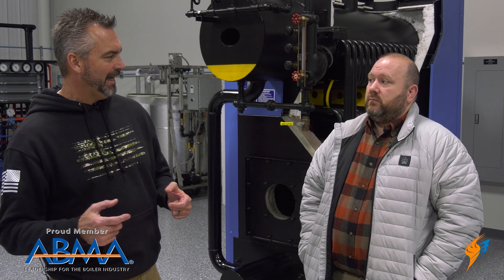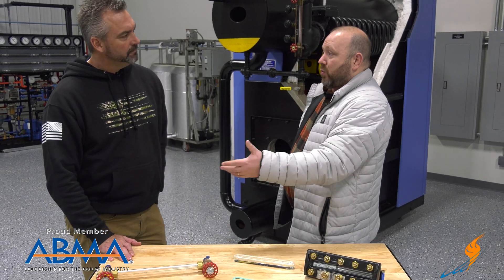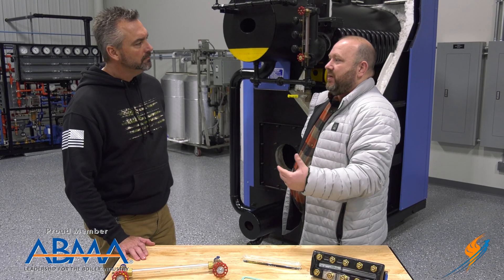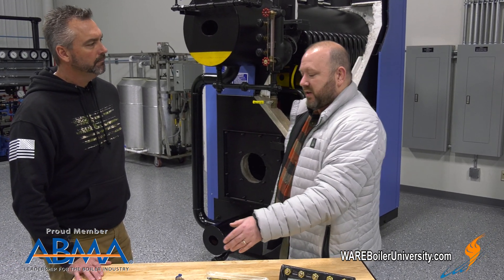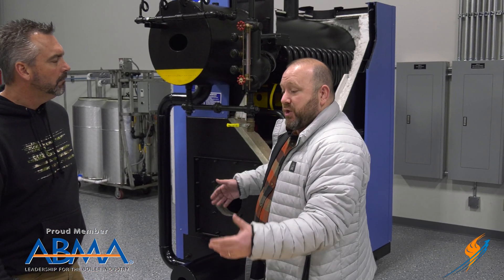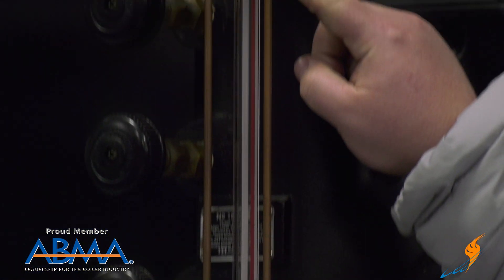One of the questions that I know is searched a lot is how do you actually measure the sight glass? Of course these lengths can all vary depending on what your boiler is. If you're putting this on one type of McDonnell Miller or another, the dimensions are going to be slightly different. Pretty much every manufacturer measures them the same way. These are United Brass valves; this back here looks like a set of Conbraco valves. You really need to take a measurement from the center of the nut on the bottom to the center of the nut on the top.